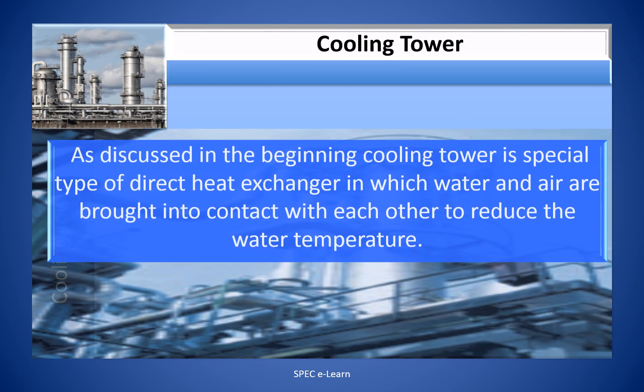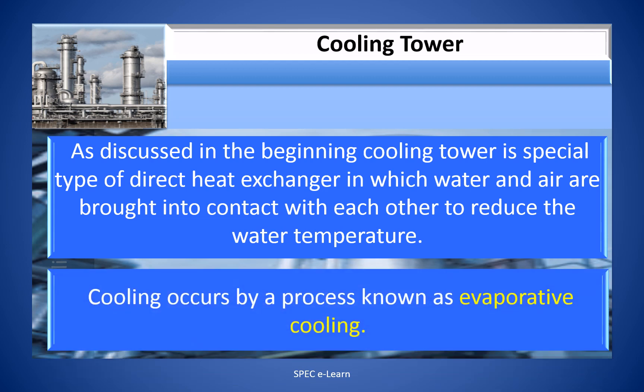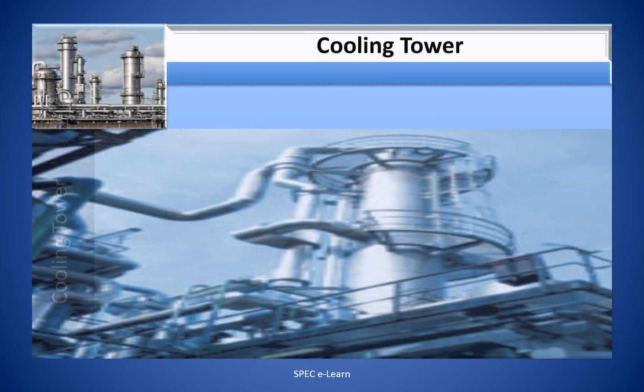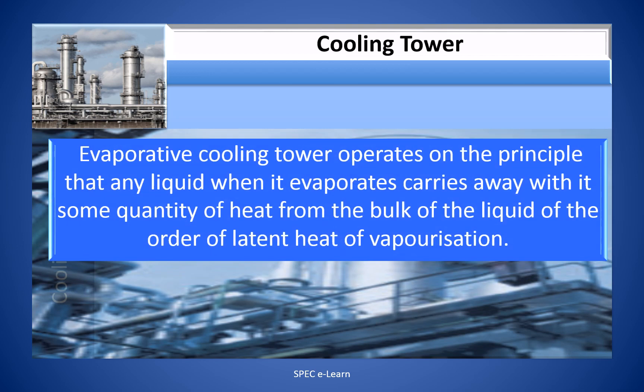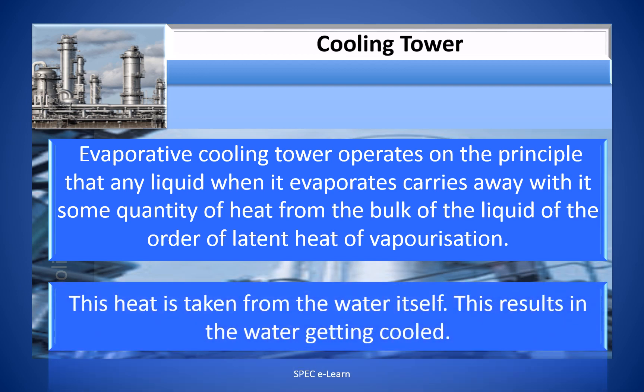As discussed, a cooling tower is a special type of direct heat exchanger in which water and air are brought into contact to reduce the water temperature. Cooling occurs by a process known as evaporative cooling. The cooling tower operates on the principle that any liquid, when it evaporates, carries away heat from the bulk liquid on the order of the latent heat of vaporization. This heat is taken from the water itself, resulting in the water getting cooled.